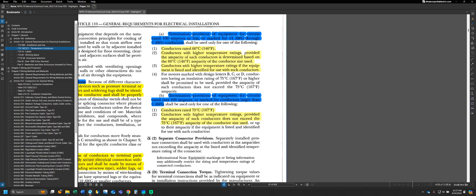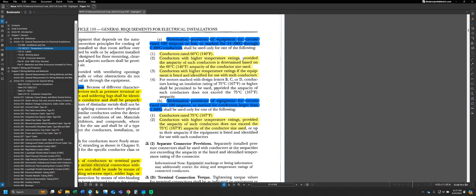Item 3 is the exception to that rule: conductors with higher temperature ratings are permitted if the equipment is listed and identified for use with such conductors. So if we're terminating to a device or piece of equipment rated for a higher temperature — say 75°C or 90°C — then we are allowed to use that higher temperature rating ampacity. For example, if both the breaker and receptacle are rated for 75°C and we're using 90°C-rated wire, we can base the ampacity on the 75°C column.